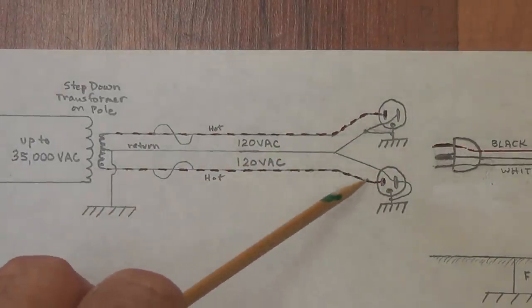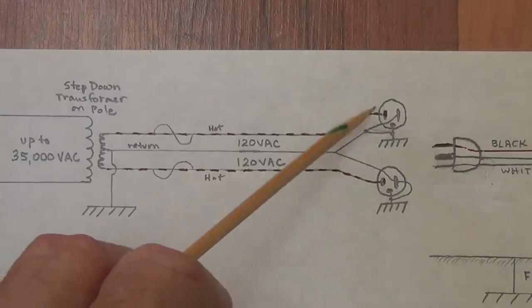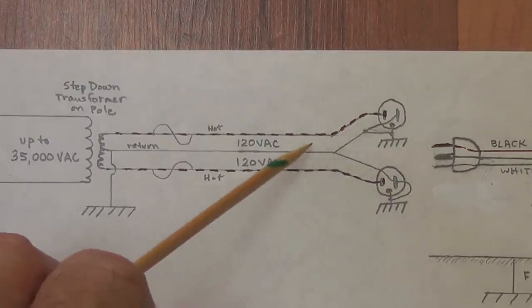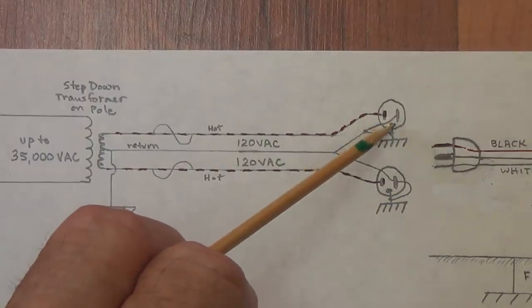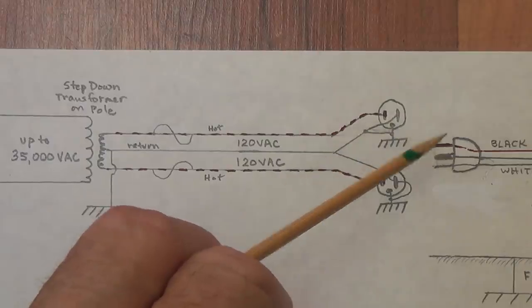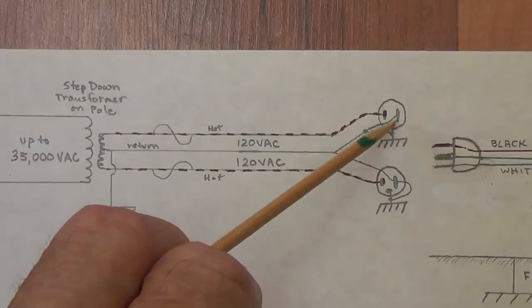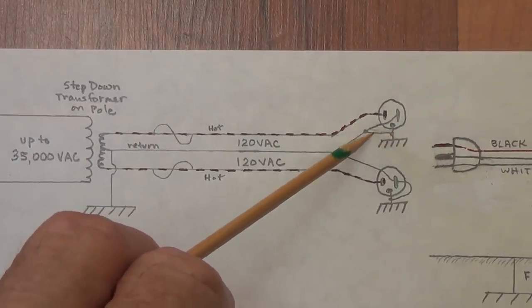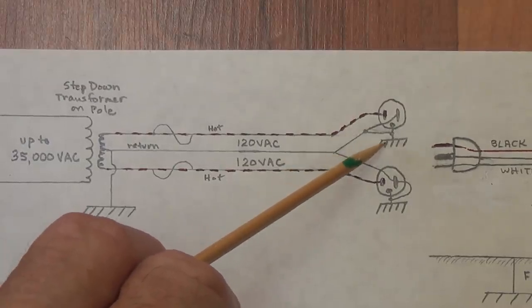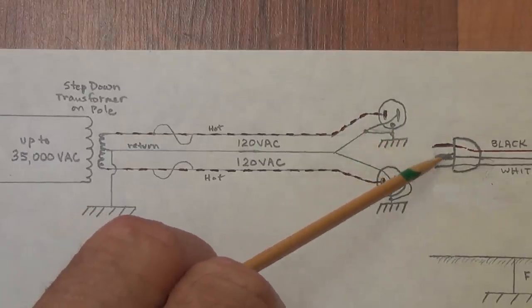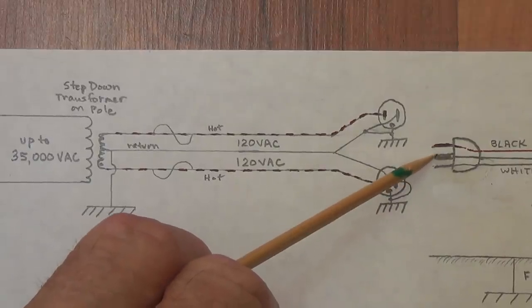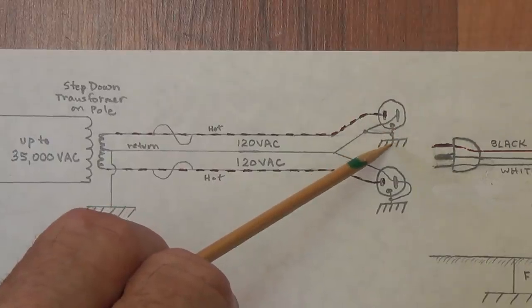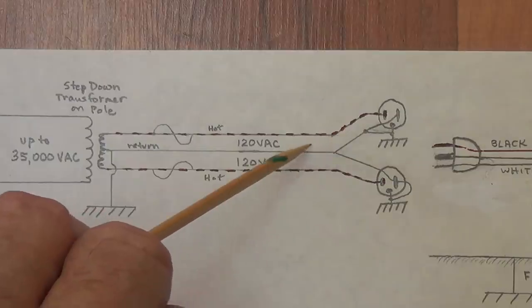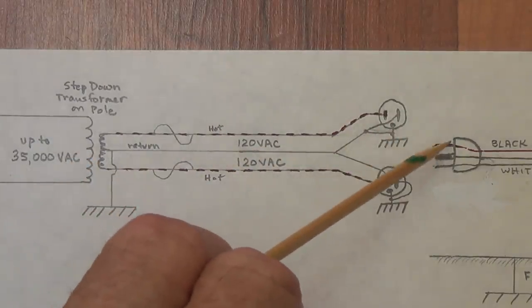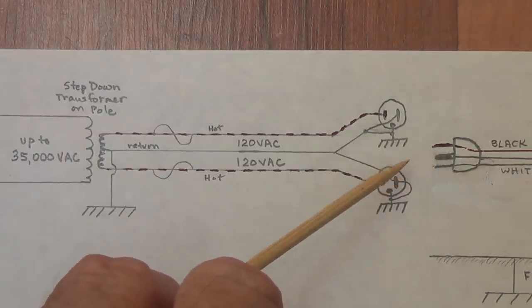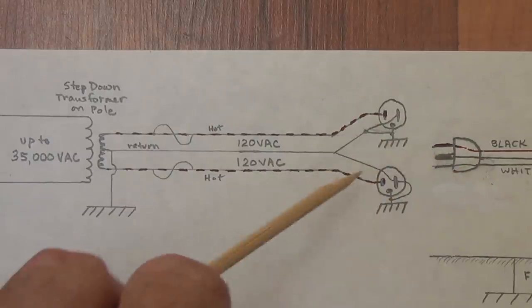Our wall receptacles are wired with the smaller of the 2 slots receiving the hot wire, the wider of the slots receiving the center tap return wire, and then a circular ground receptacle at the bottom that we will plug our 3-wire plug into, that not only is earth grounded but also connected to the center tap return. This is for safety purposes. This gives 2 routes for the electricity to return. If electricity shows up on this ground lug, it shouldn't, but if it does, it can pass through the ground back here to the center tap, or it can pass through the return wire to the center tap. So, like I said, for safety reasons, it's like a double provision here of return capability in case of a short circuit.